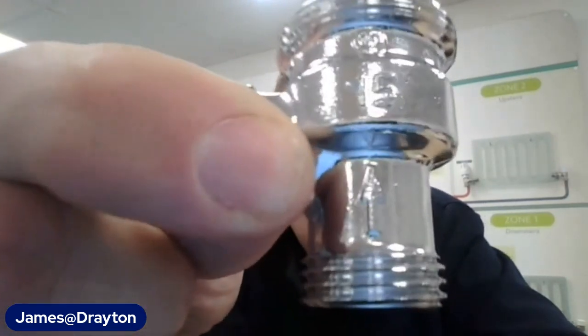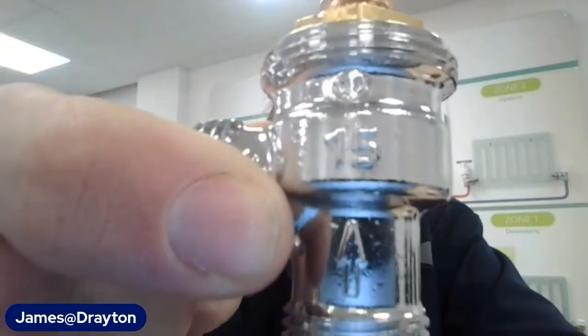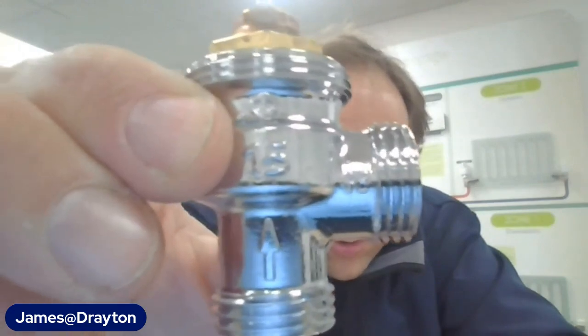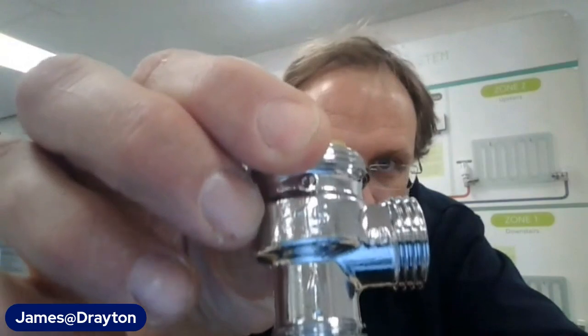The first thing is that they are unidirectional. So if I zoom in a bit on that, you can see that this is the 15mm angled body. Now, we're used to the idea that all of Drayton's angled bodies are bidirectional. Well, these aren't. These are unidirectional, meaning that you need to respect and follow the flow direction arrow. And the upshot is, and this is what I've been hearing from customers, if you get them the wrong way around, you don't get the right amount of flow into the radiator, and they can be noisy. So you really need to make sure that you respect that flow direction arrow.